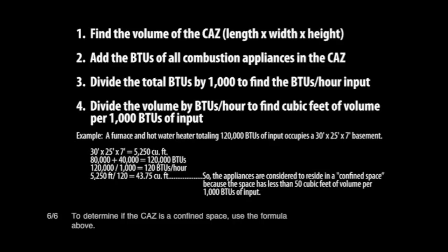To determine if the CAZ is a confined space, use the formula above. Step 1: Find the volume of the CAZ by multiplying length times width times height. Step 2: Add the BTUs of all combustion appliances in the CAZ. Step 3: Divide the total BTUs by 1,000 to find the BTUs per hour input. Step 4: Divide the volume by BTUs per hour to find the cubic feet of volume per 1,000 BTUs of input.